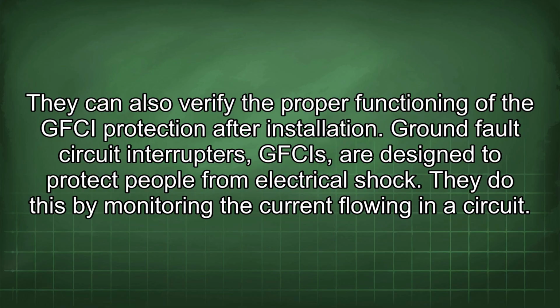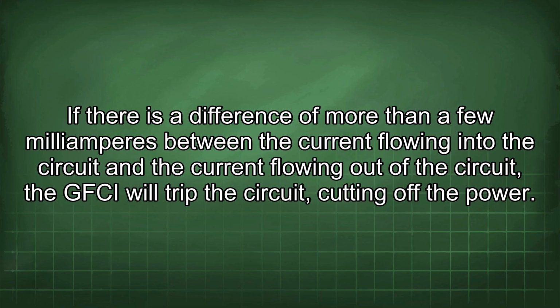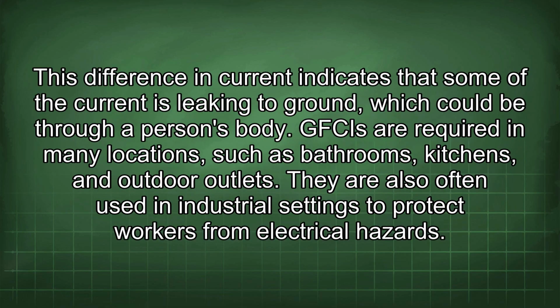Ground fault circuit interrupters, GFCIs, are designed to protect people from electrical shock. They do this by monitoring the current flowing in a circuit. If there is a difference of more than a few milliamperes between the current flowing into the circuit and the current flowing out of the circuit, the GFCI will trip the circuit, cutting off the power. This difference in current indicates that some of the current is leaking to ground, which could be through a person's body. GFCIs are required in many locations such as bathrooms, kitchens, and outdoor outlets. They are also often used in industrial settings to protect workers from electrical hazards.